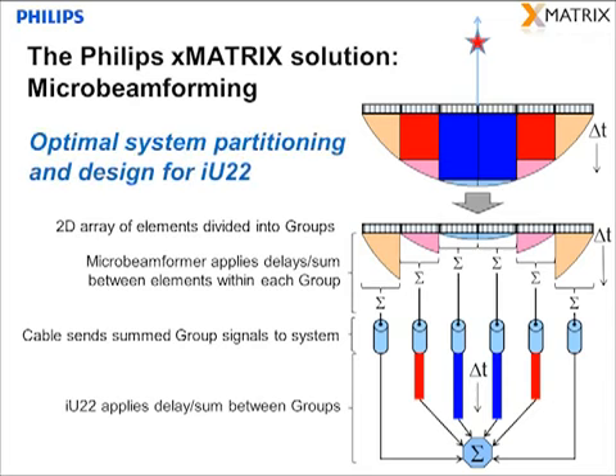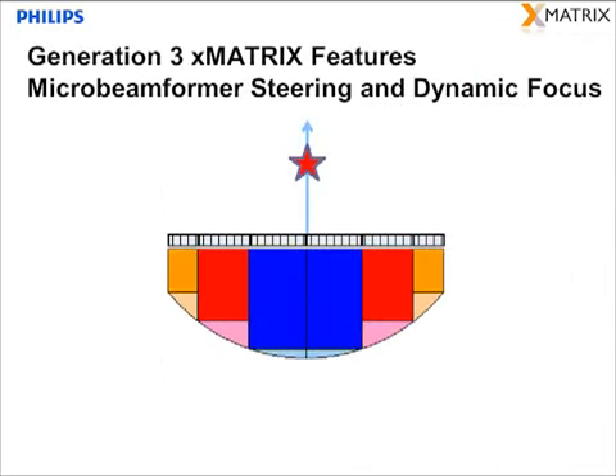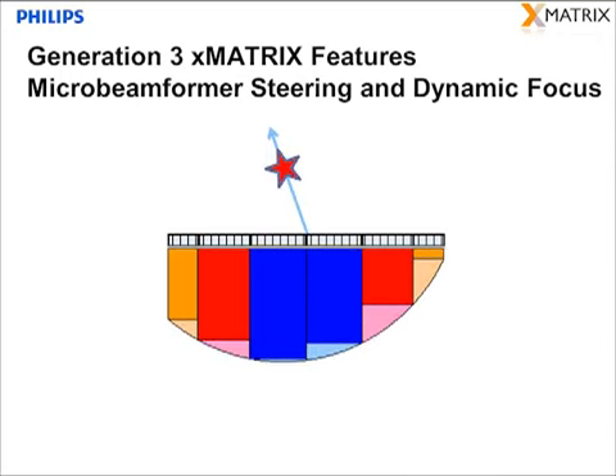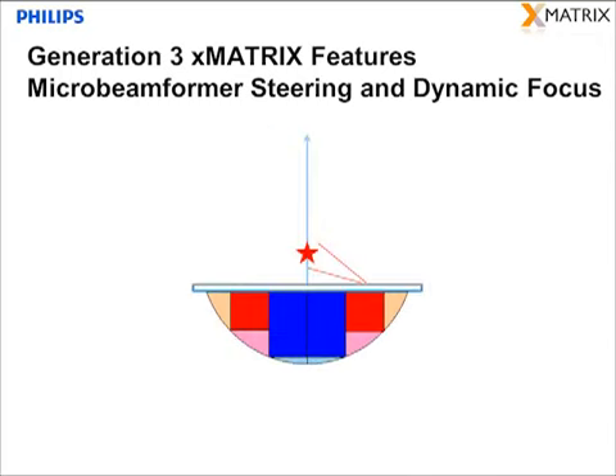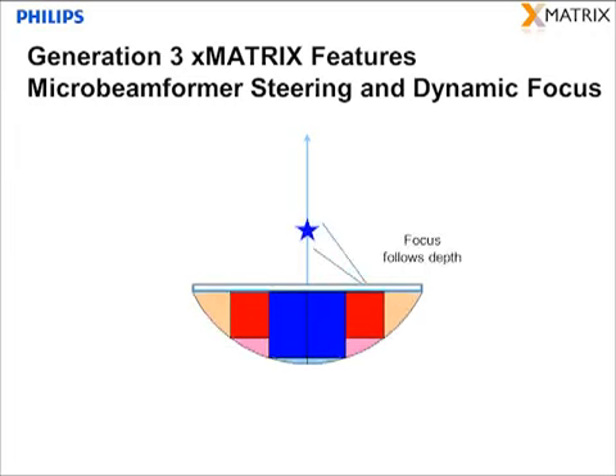This is the optimal system partitioning and design for the IU-22. By controlling the relative timing of the microchannels and groups, we can steer and focus the acoustic beam anywhere within the field of view. For example, to steer, we make the delay curve asymmetrical. And to move the focus with depth, we change the partitioning of the delays between the microbeamformer and the system to flatten the delay profile.